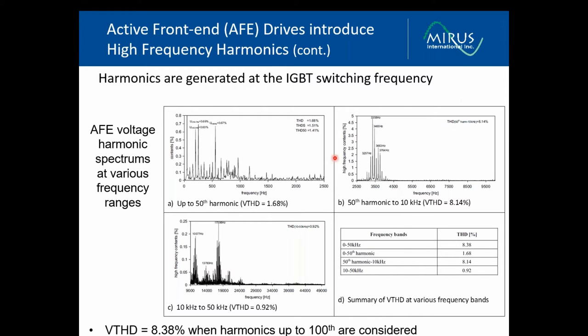However, when measurements were taken above the 50th harmonic, in the band from 2.5 kilohertz to 10 kilohertz, we see a large high level of harmonics introduced, which reflect the switching frequencies of the IGBTs. In this case, it was around 3.4 kilohertz. There was enough distortion here. You can see the highest is at 5% THD. The total harmonic distortion in this band was 8.14%. Above the requirements of the marine certifying bodies, granted just slightly above, but these are high-frequency harmonics.